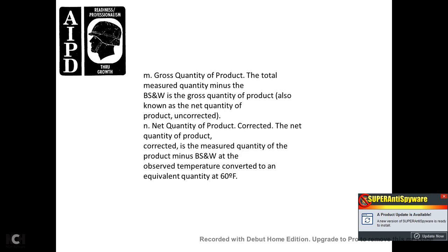9. Gross quantity of product is the total measured quantity minus the bottom sediment and water. 10. Net quantity of product is the corrected measured quantity of the product minus the bottom sediment and water, converted from the observed temperature to an equivalent quantity at 60 degrees Fahrenheit.